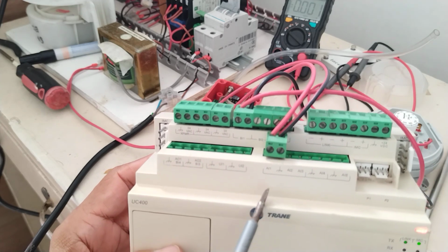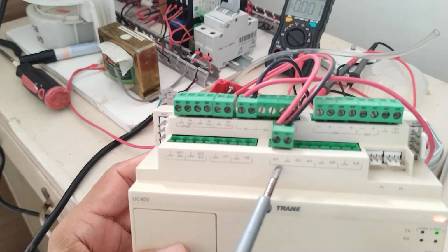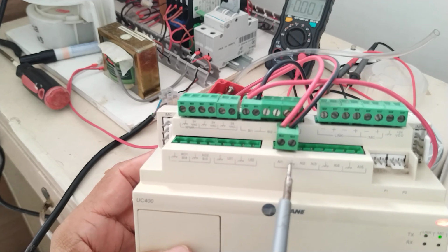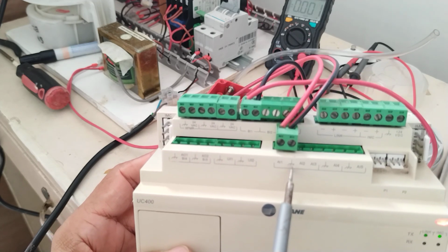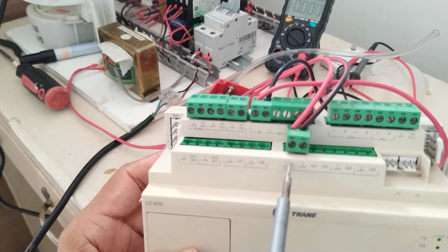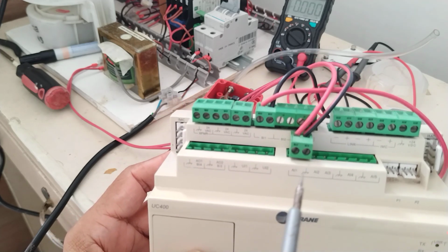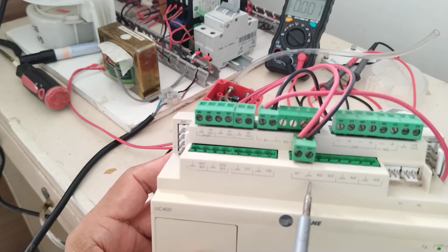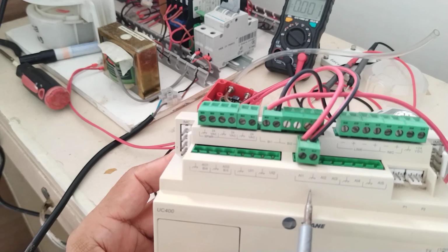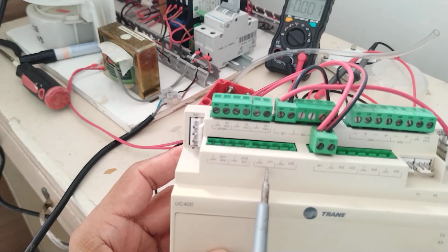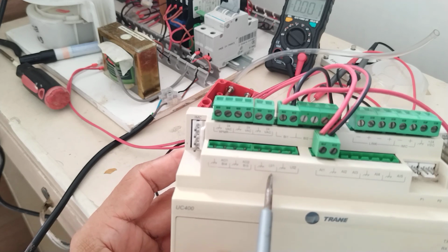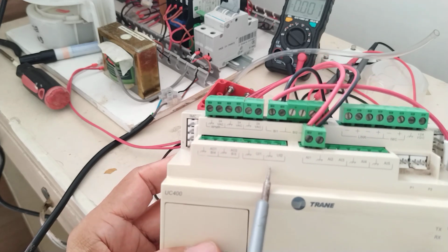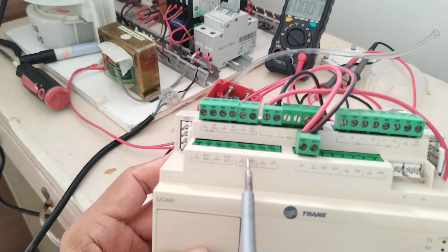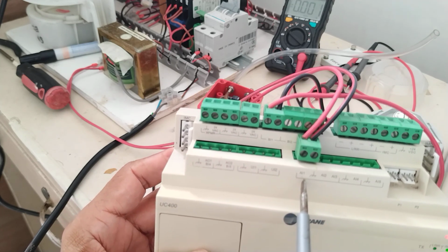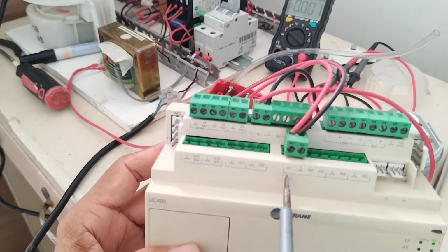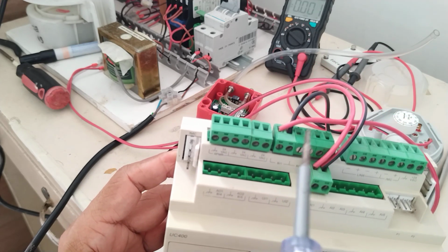Now, make sure to check the proper termination. So, this symbol represents the common, okay, or the ground, but this one is common. Then, the A1 is the signal, okay? So, signal is the 0 to 10 volts. Then, this one is the common, okay? Now, we can also connect it in a universal input. Because universal input, as you know, we are using it also for digital or analog input. So, you can use also universal input. But now, I decided to connect it in analog input number 1. Okay? Then, for the differential pressure switch, binary input number 1.